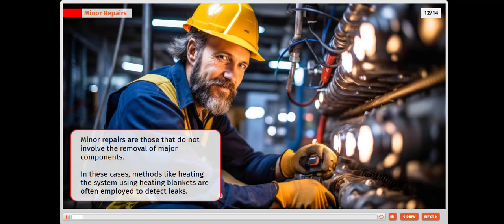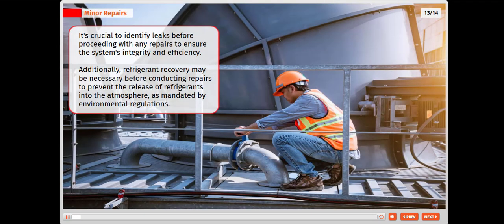Minor repairs are those that do not involve the removal of major components. In these cases, methods like heating the system using heating blankets are often employed to detect leaks. It's crucial to identify leaks before proceeding with any repairs to ensure the system's integrity and efficiency. Additionally, refrigerant recovery may be necessary before conducting repairs to prevent the release of refrigerants into the atmosphere, as mandated by environmental regulations.